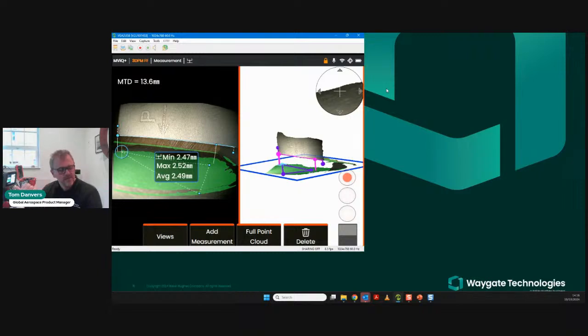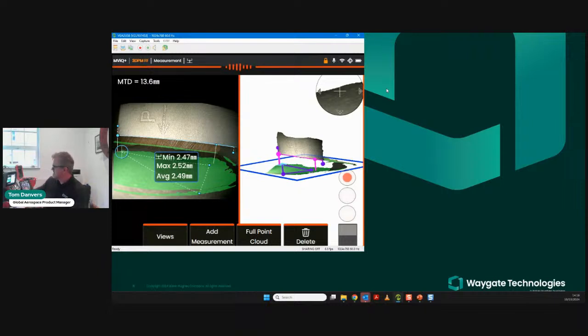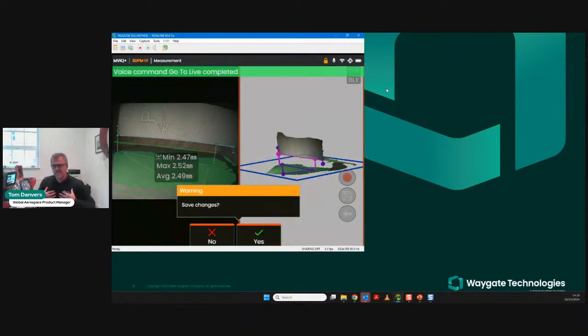So what I'll do is take it back to the live state and change the image and do a point-to-line measurement. So let's, hey mentor, go back to live. Now it's asking if I wanted to save the image, which is perfectly normal. Rather than tapping the screen, just to demonstrate another activity, you can say soft key number 3, or number 2, so that we have these 4 soft keys on the bottom of the screen. And obviously, what you see on the bottom of the screen depends on all sorts of factors, where you are in the device. So here we have a prompt that says yes or no to save an image. I'm going to want to say no, and I could have obviously just touched the screen, but just to demonstrate to you another command that works.